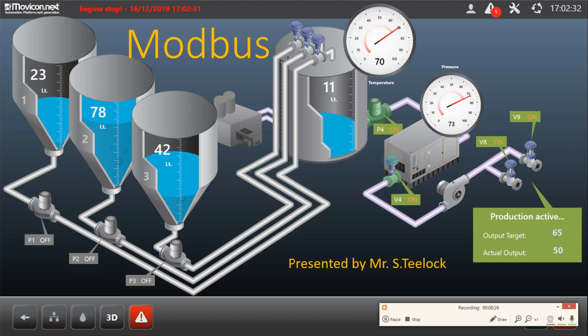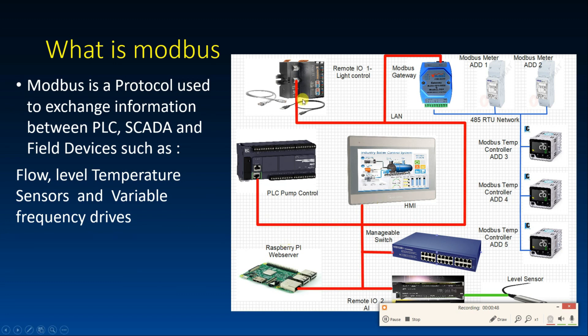Today I will talk about Modbus. Modbus is normally used in industrial processes — it's a common protocol among RTUs like temperature sensors and flow meters. As you can see in this window, we have Modbus TCP and Modbus RTU. The RTU is based on an RS-485 network, which is a differential communication. Two wires run in parallel, connecting all the devices together.